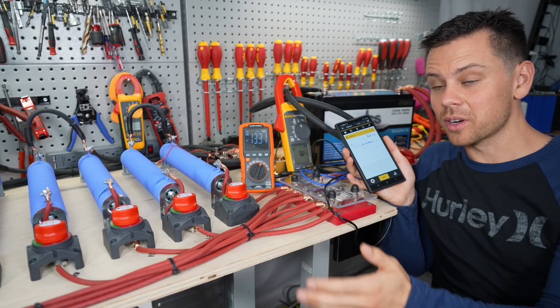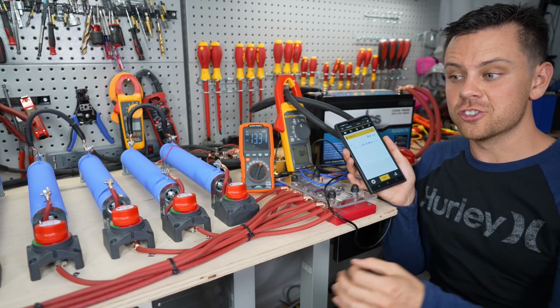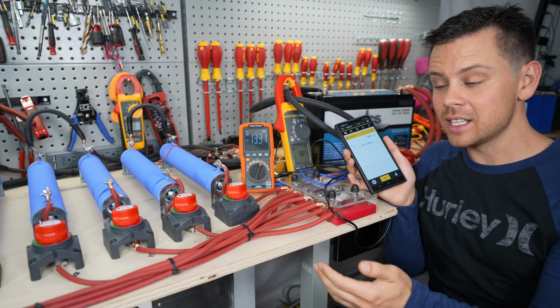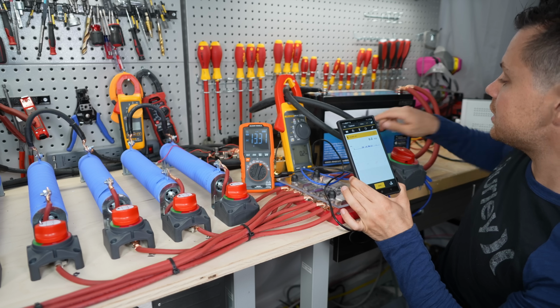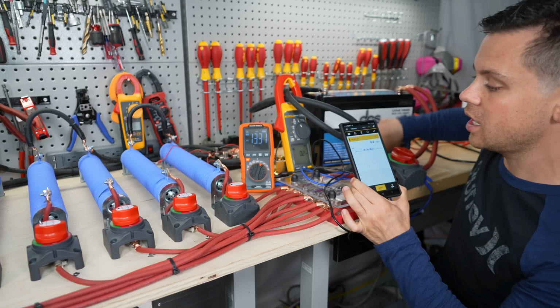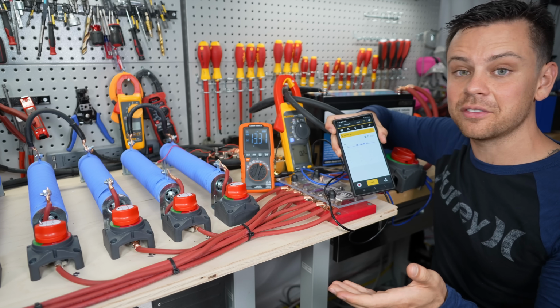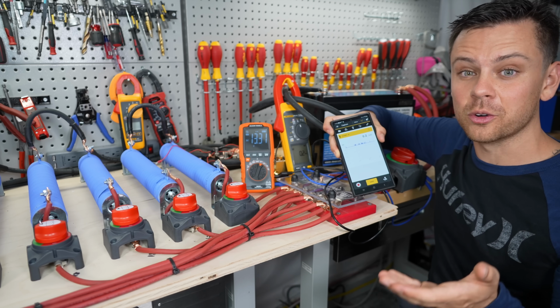Now for the next test, we're gonna turn on all the resistors and try to capture the peak current that this thing can deliver, because it says it's rated for 1000 amps. So we're gonna see if we can get at least 500 amps for at least 1 or 2 seconds.